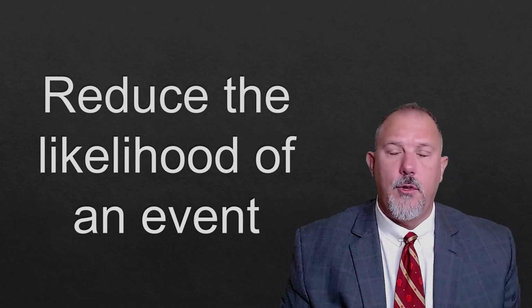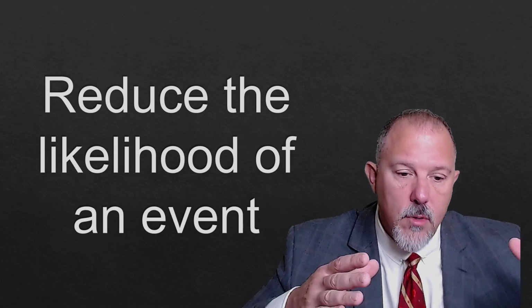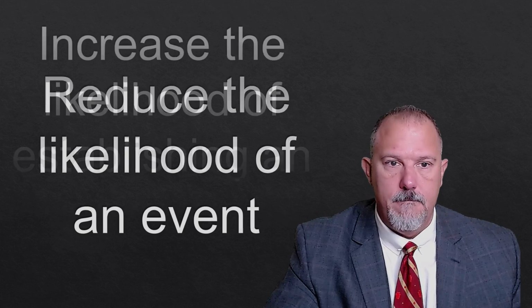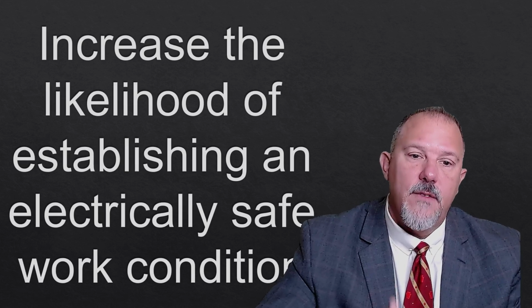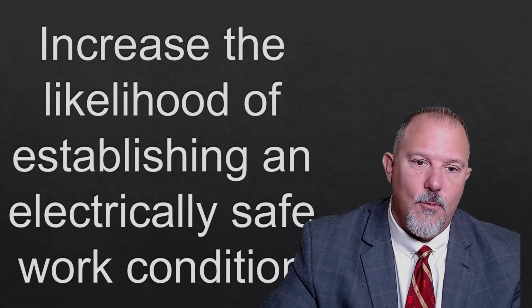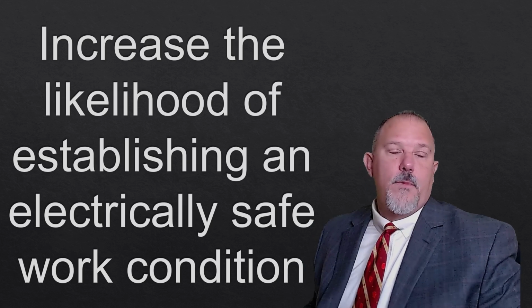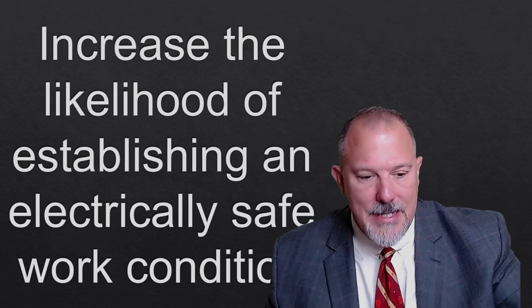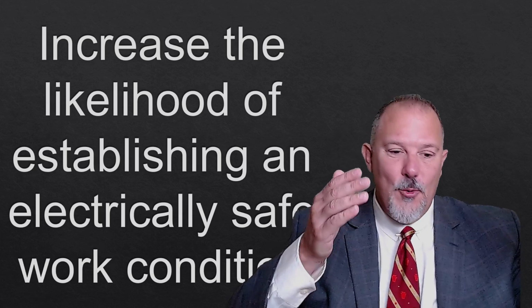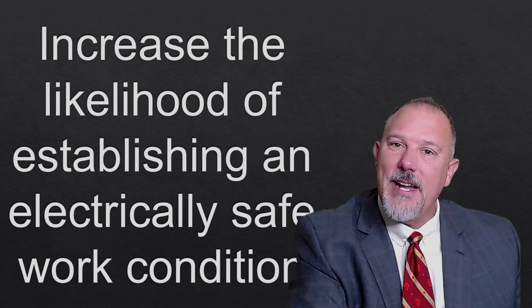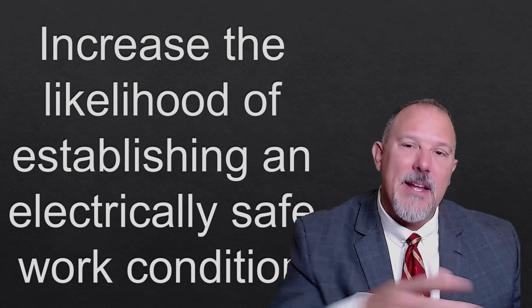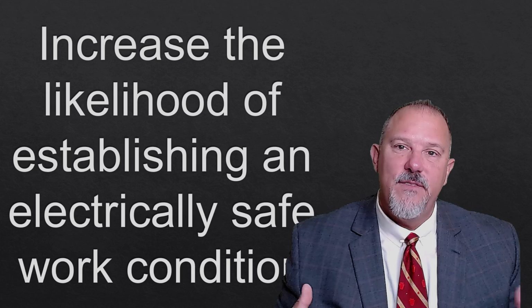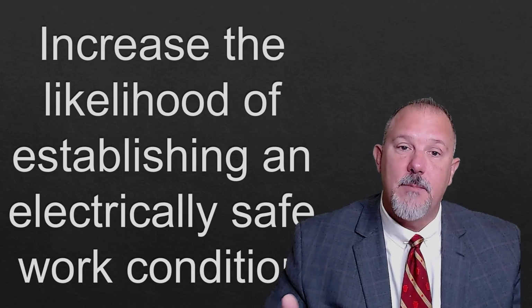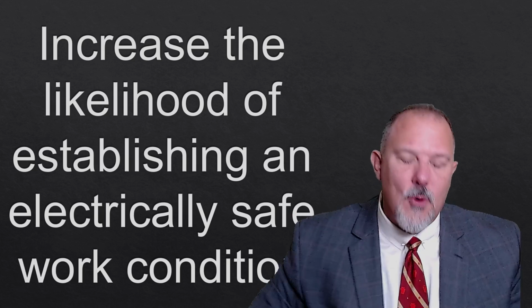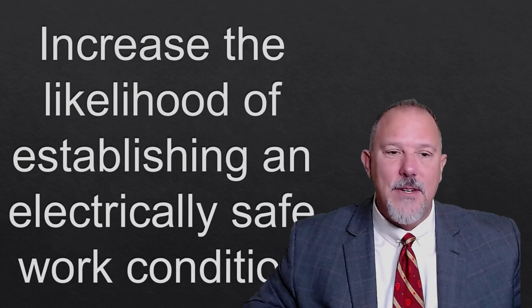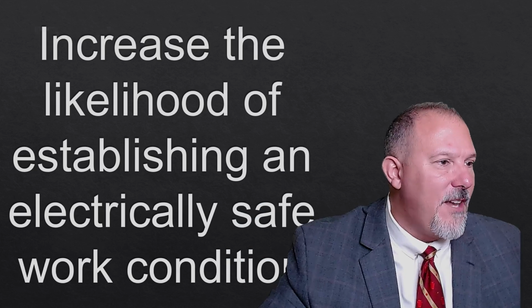Provide barriers wherever you can. Give them more space wherever you can. You want to increase the likelihood of establishing the electrically safe work condition. Increase the likelihood by putting disconnects in. Make it easy to do a lockout tagout procedure. Complex lockout tagout procedures can be confusing, especially if the one-line diagram isn't updated. Updating the single-line diagram is not required by the National Electrical Code, but it can increase the likelihood of establishing an electrically safe work condition.